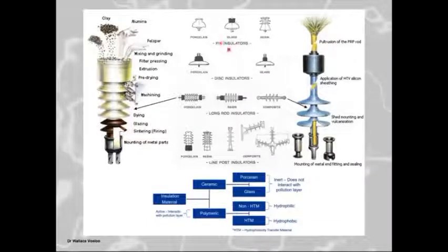But we've got the pin type insulators, which is basically a metal pin. And then the metal pin has got lead around the thread. And then you've got either a porcelain or a glass or a resin insulator, which then screws onto this pin. This insulator that screws onto the pin is made from a very good insulating material with good shed profiles on, and normally has a coupling point at the top, which you can rest the conductor in and then basically wrap lock tie it onto it. These pin insulators are normally very prone to high lightning areas. So you normally find that you get a lot of puncturing on them, but I'm not going to go into that too much.